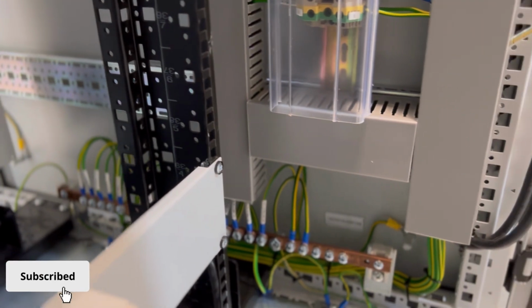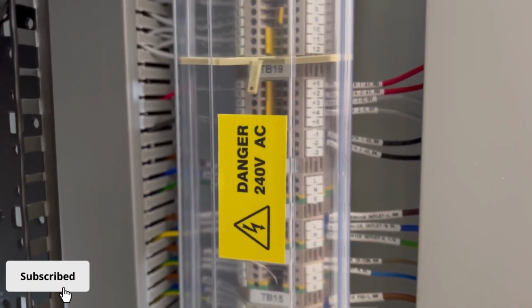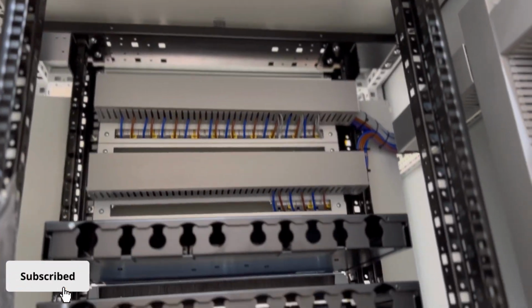Okay, so this is the basic information for your testing. So this is a vendor testing, factory acceptance testing. This is the terminal, as you can see in the video. All terminal black, all ferrules, wires, it's the same, because we need to identify what is the size of the cable, cable wires. Thermostat is working, the fan is working, the light is working. So everything is to be checked as well, visual inspection, verifications, and you need to run all the system.